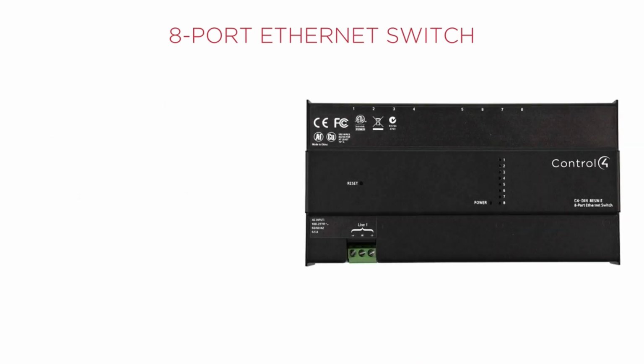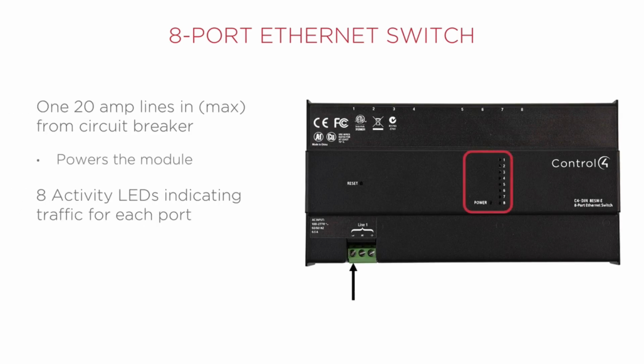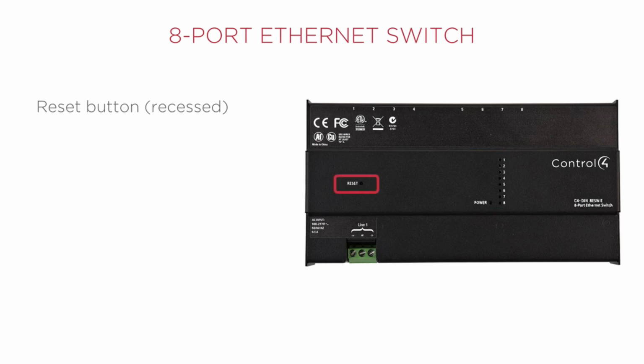The 8-port Ethernet switch accepts a 20 amp line in from the circuit breaker, and has 8 activity LEDs indicating traffic for each port. If the LED is orange, that port is active. There is a recessed reset button that can be pressed to reboot the module, or pressed and held to reset the module to factory defaults.